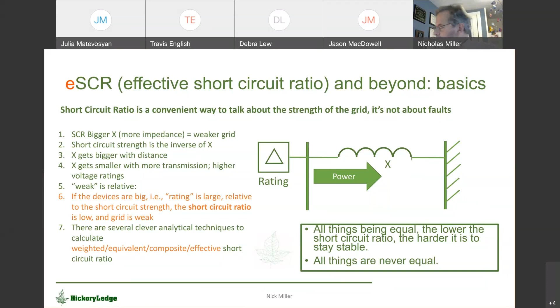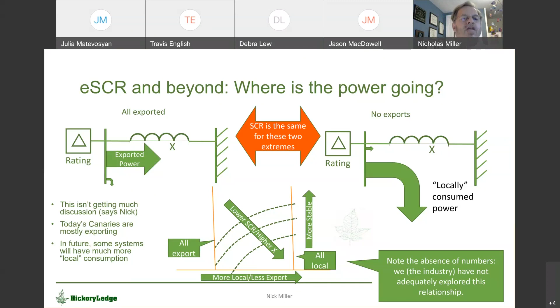So on the left top of this figure is the condition that we're experimenting with, where all of the power is being pushed from some remote place to a load center. You can't get wrapped around the axle of thinking that that is equivalent to the problem on the right, where the power being generated is being consumed more or less electrically where it's generated, and the rest of the system is someplace remote. That's the Hawaii problem, all right, where X is going to infinity. That's a good application for grid forming, but it's not the export problem. So there's a bunch of other words there that come into play on this slide, but fundamentally don't convolve the problem of getting power out of a remote place to a massive grid like we have in the West, like we have in the Eastern interconnection, with a situation where the entire system is dominated by the left-hand side of the figure. So let's go on to the next slide.